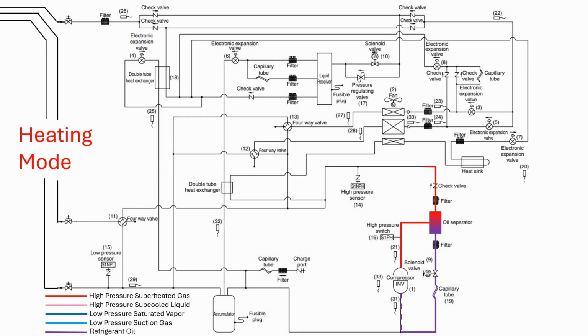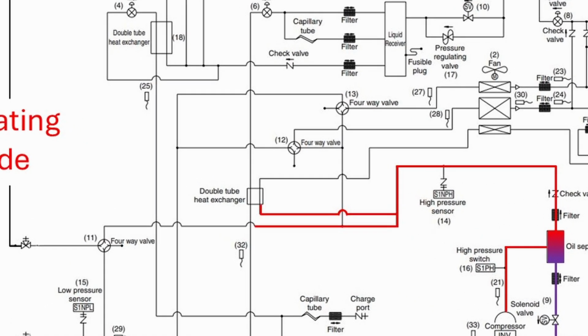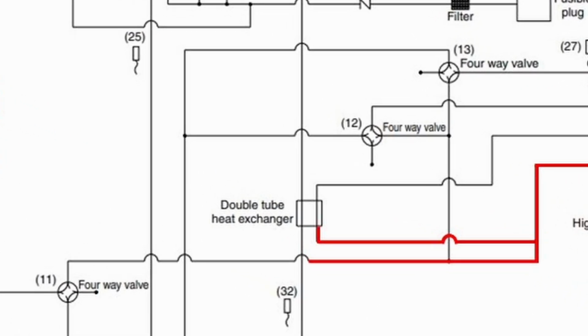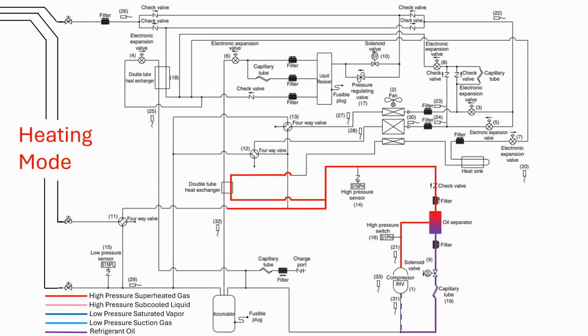As the refrigerant leaves the oil separator, it too passes through a filter or bullet strainer on its way to its first stop, which is a tube-in-tube heat exchanger or subcooling coil. From the tube-in-tube heat exchanger, the refrigerant travels to its first section of outdoor coil.